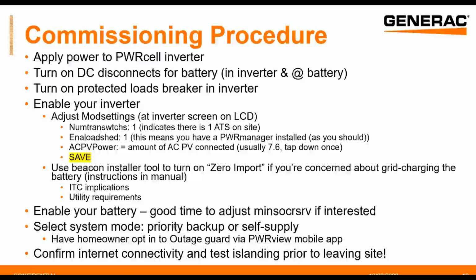And then you'll adjust a set point called AC PV power, and you're going to set this to match the amount of AC PV that's interconnected on the load side of the ATS. For our system, this needs to be 7.6 kilowatts AC or less on the load side. If you have like 12 kilowatts of microinverters, you can interconnect up to 7.6 kilowatts AC of them on the load side of the ATS, and the rest on the line side, export it right out to the meter.